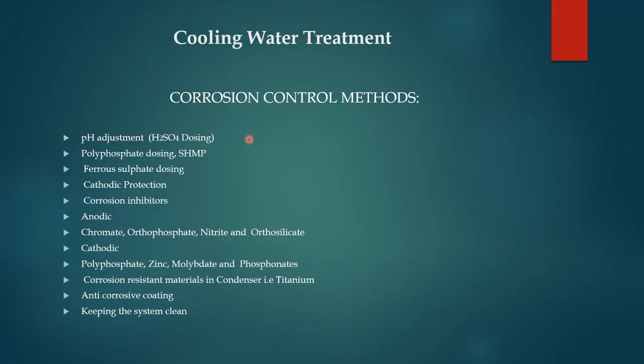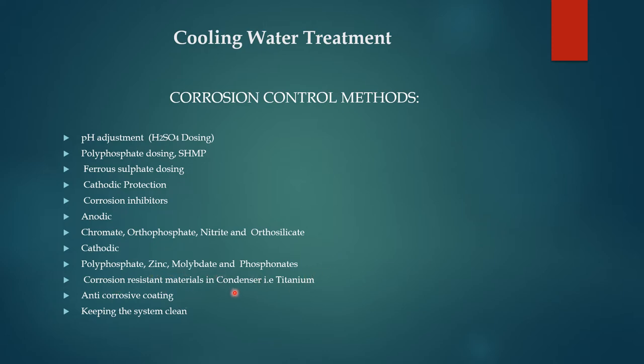Corrosion control methods include: pH adjustment using H₂SO₄ dosing (sulfuric acid used to maintain pH), polyphosphate dosing, sodium hexametaphosphate dosing, ferrous sulfate dosing, and cathodic protection. Corrosion inhibitors include anodic inhibitors such as chromate, orthophosphate, nitrite, and orthosilicate, and cathodic inhibitors such as polyphosphate, zinc molybdate, and phosphonate.